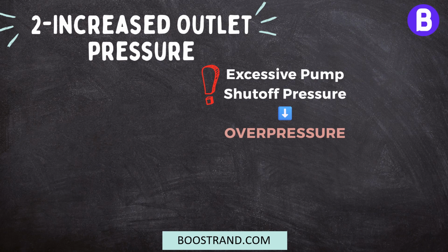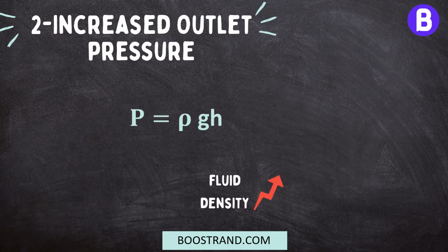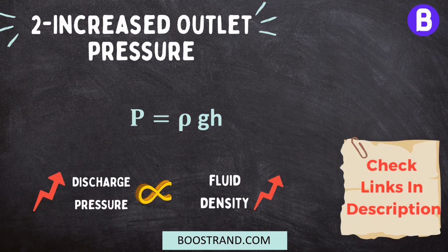An excessive pump shutoff pressure can cause overpressure in the discharge system and can lead to huge impact during project execution. If the fluid density increases, the pump's head will remain the same, but the pressure will increase. This is because pressure is a function of head and fluid density.